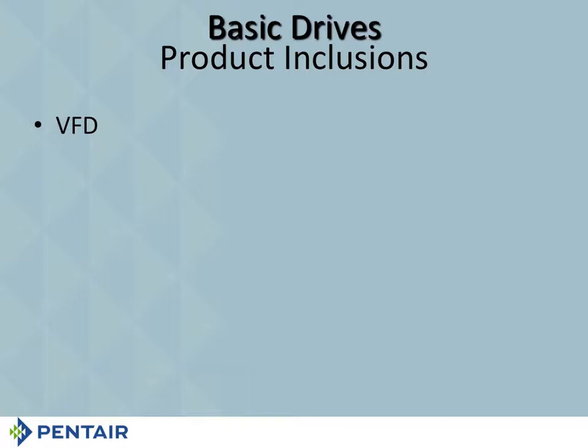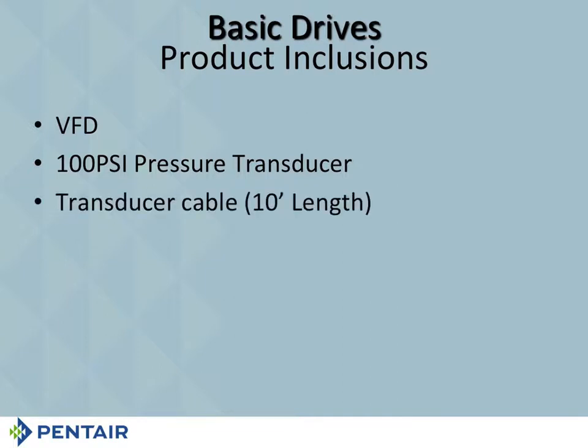We're going to give you a 100-pound transducer. That transducer comes with 10 feet of cable. Now, I'm going to tell you right up front that if you're further than 10 feet away, buy another cable. Don't use the 10-foot cable. Don't try and splice it. Make sure you're using the correct size cable.